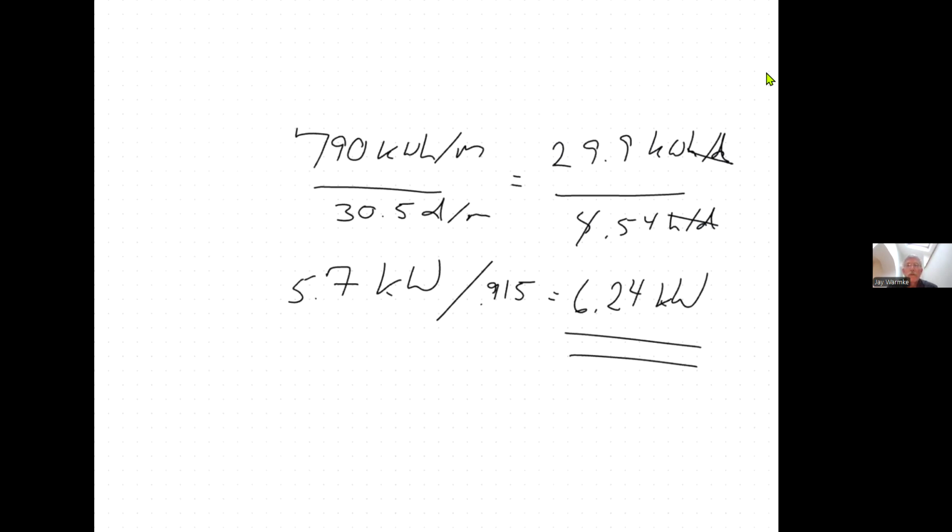Now, if you end up with 5.7 kW and then you multiply it times the derate, which is something people do a lot, you'll get a smaller number. Well, logically, that should make sense, right? If everything was great, I need 5.7, but because I lose some of the power, I can get by with a smaller array. Yeah, that's just all backwards. So hopefully you'll realize that as you're working the numbers.